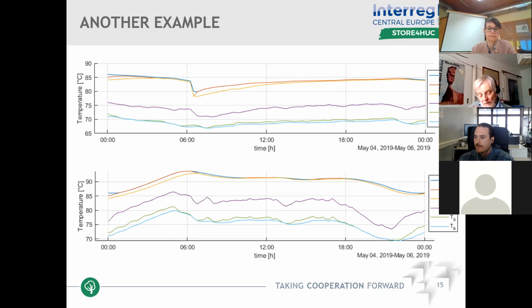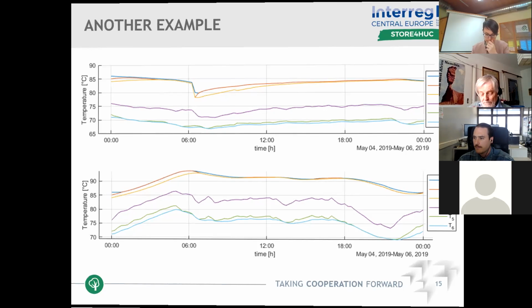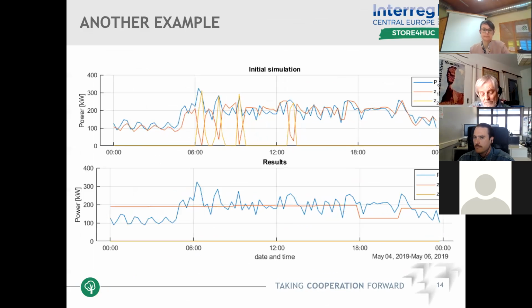I just wanted to say that the effect of leakage of heat to outside air is not that dominant compared to the gains you get with changed operation of the boiler. So the optimization chooses to do that and rather raise the temperature a bit at certain moments. Yes, of course.